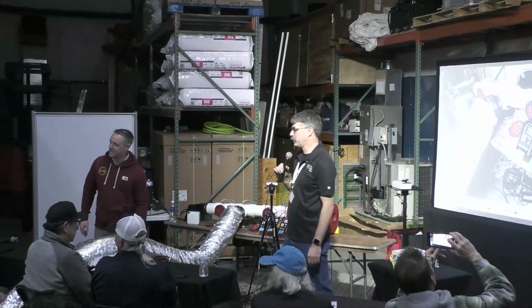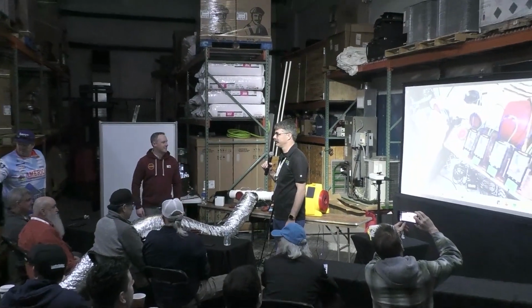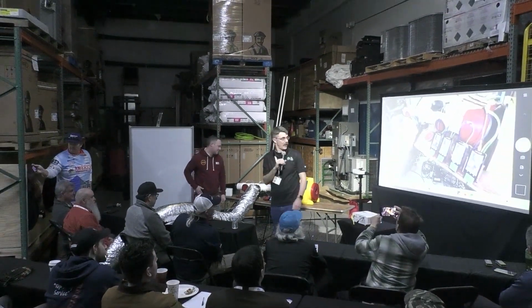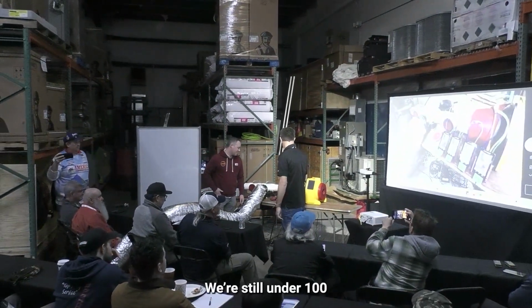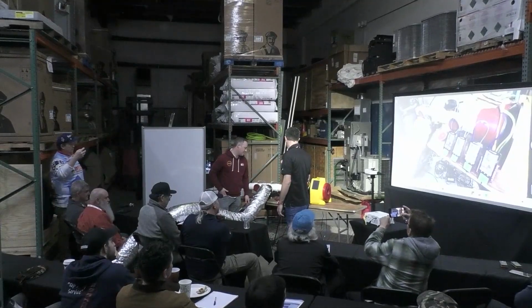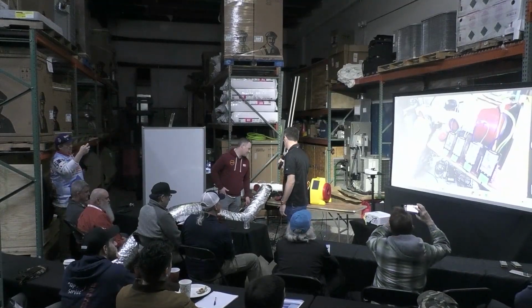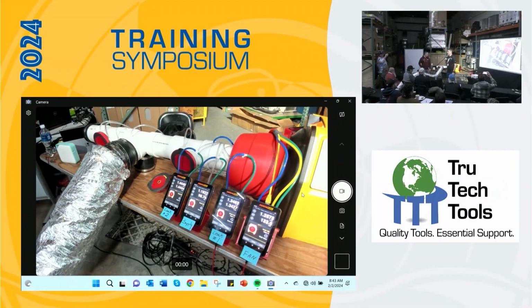One big bowl of spaghetti duct coming up. How are we looking now? Now we're back under 100. We're up to almost 1.2 inches of static by turning it into spaghetti.